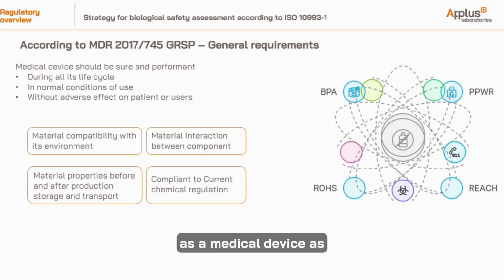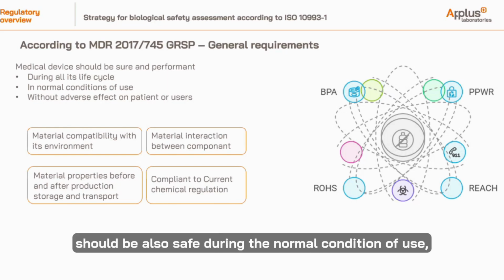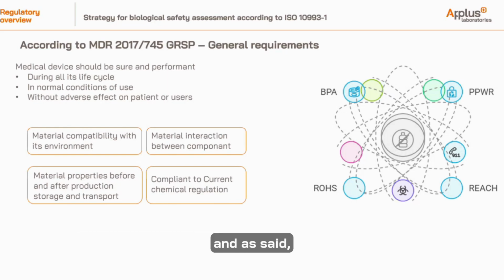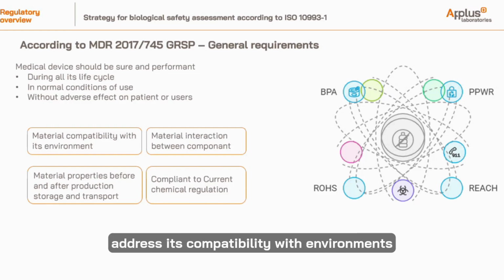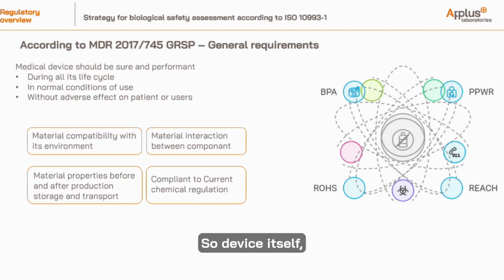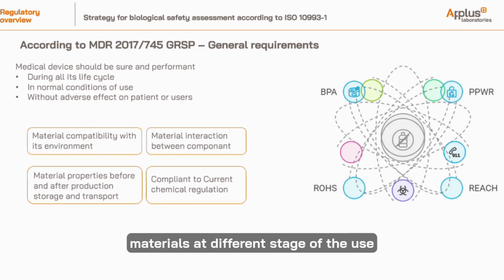And as a risk category, the medical device, as said, should be safe and performant during all its life cycle. That means it should also be safe during normal conditions of use and should not induce adverse effects on patients or users. So considering biocompatibility should address the compatibility with the environment of the components of the medical device, and of the medical device itself, the materials' interaction between the different components, accessories, and parts of the medical device, and the properties of the materials at different stages of use, before, after, during storage and transport, to help anticipate the risk of degradation of the product.